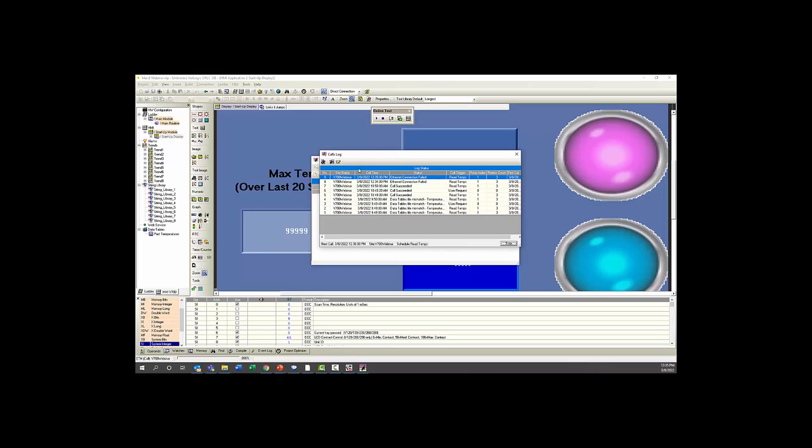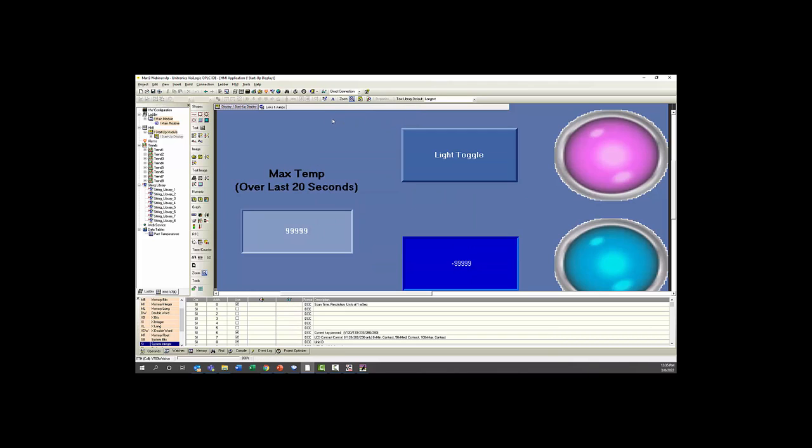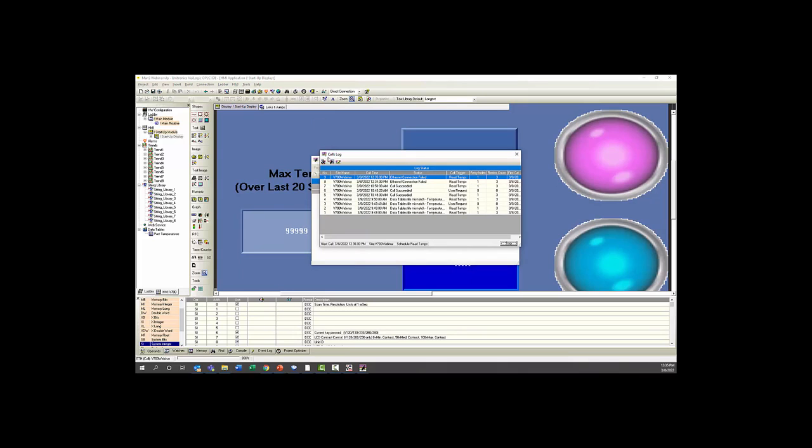And that is because we are using online mode in VisiLogic here that is also operating on port 20256. So if we go and disable that and then return to our data export app, we can select the force call here, select the PLC we want to force a data call to. And now you can see the call succeeded because that port is now available. So if you want to be able to run all of these things simultaneously, you would want to set up several different sockets so that you can use a different connection port for each method of data collection or PLC communication that you want to use.